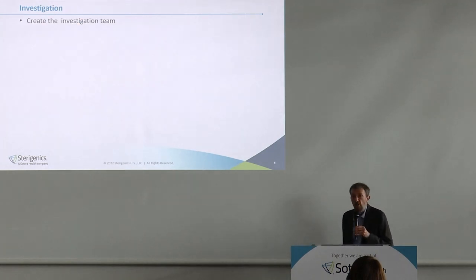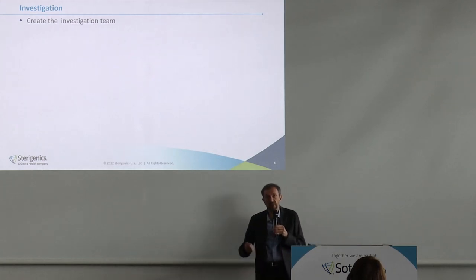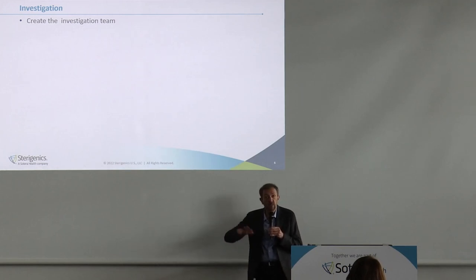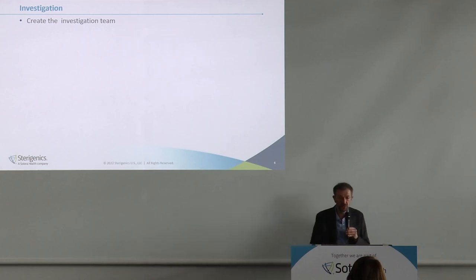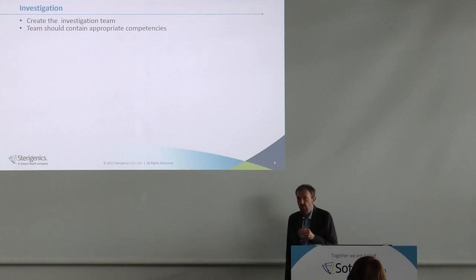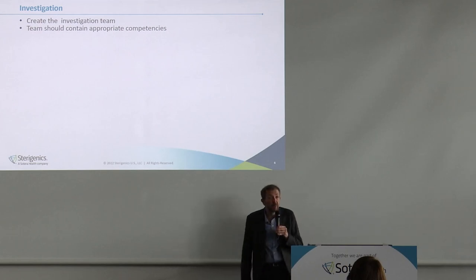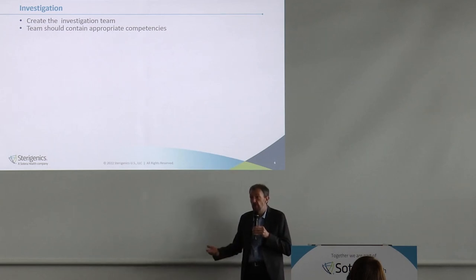Investigation is not a single-person task because it will involve equipment, people, and the laboratory — all stakeholders playing a role need to be part of the team. It's going to be a cross-functional team that investigates, and each team member should be competent in what they are reviewing. If we ask someone from the lab to help with the investigation, it needs to be a trained person.